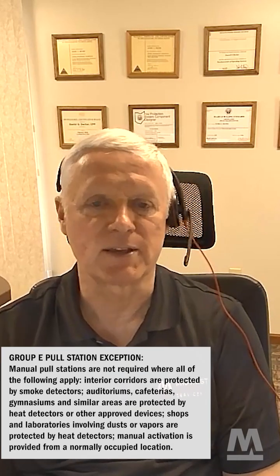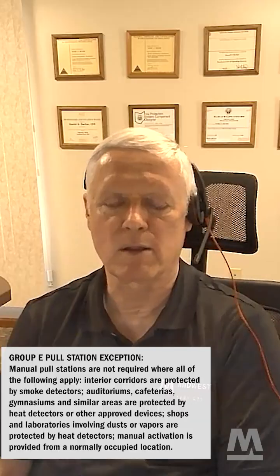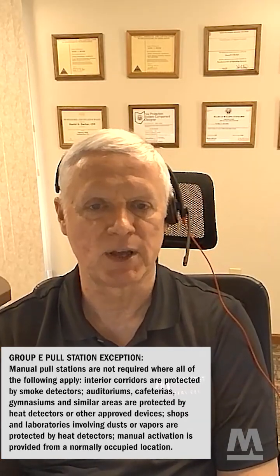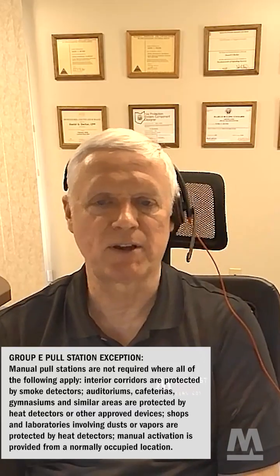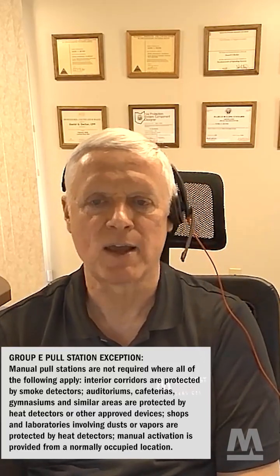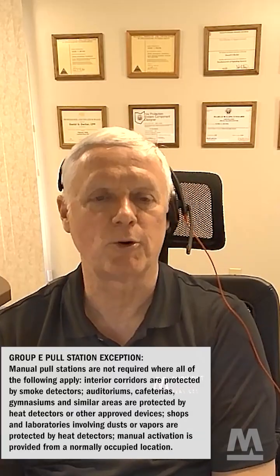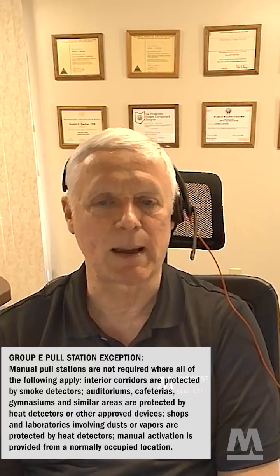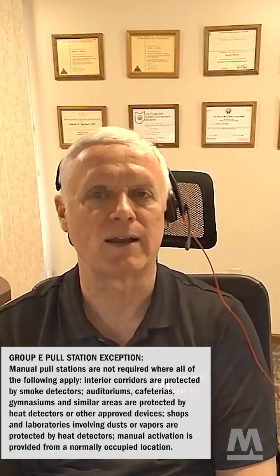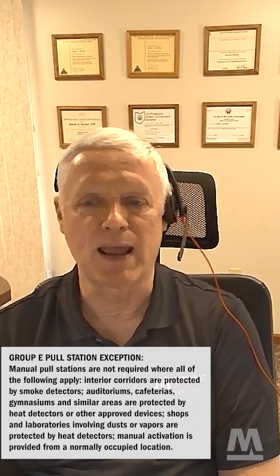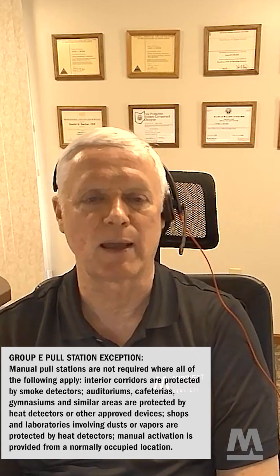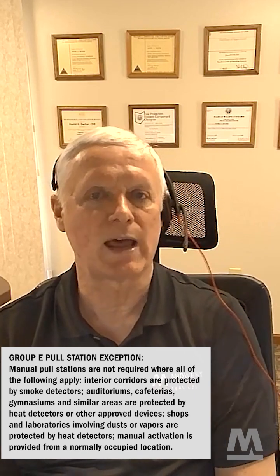There is a pull station exception for Group E that says the pull stations are not required where all of the following apply. One, your interior corridors are protected by smoke detectors. Two, auditoriums, cafeteriums, gymnasiums, and similar areas are protected by heat detectors or other approved devices. If you've got shops and laboratories that involve dust and vapors, they are protected with heat detectors, and manual activation is provided from a normally occupied location. So that's one way of not putting pull stations at all the exits in schools, because we all know kids would never pull a pull station, right?